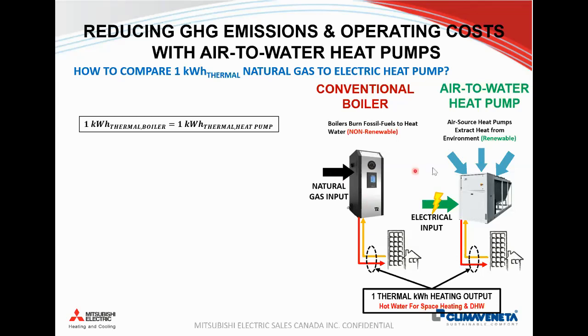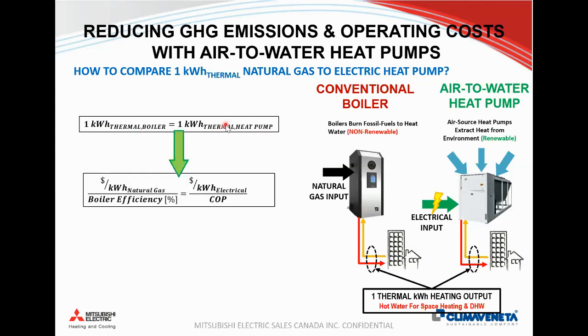So how do we compare the energy sources? If this is the same amount of heat provided from either the boiler or the heat pump, we look at our boiler, take our total delivered natural gas price in dollars per kilowatt hour delivered, and divide it by the boiler efficiency. That tells us how much money we're spending to provide 1 unit of heat.